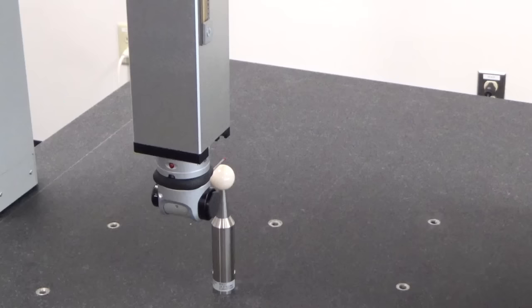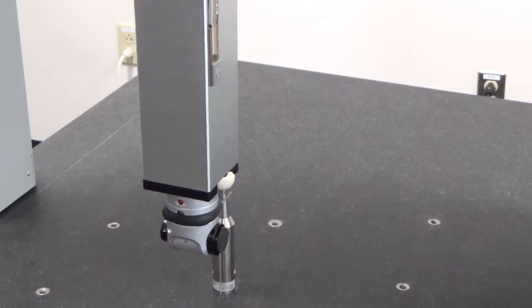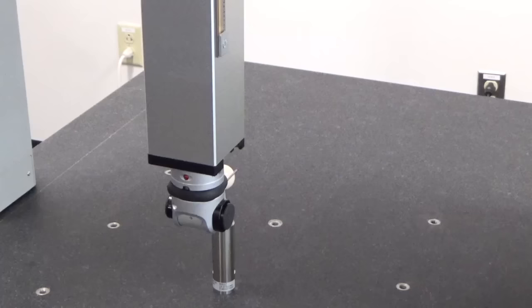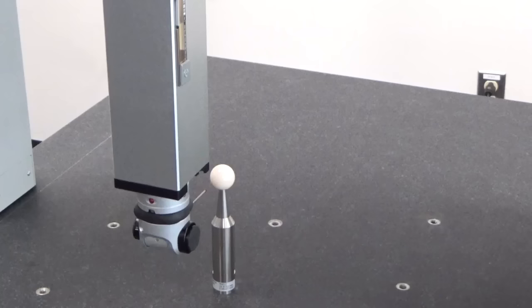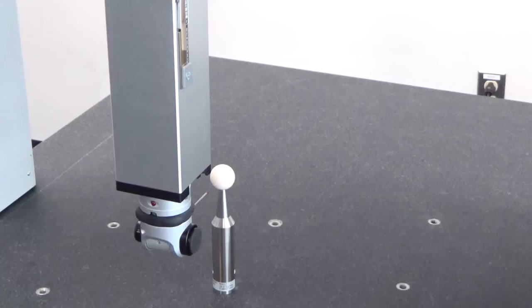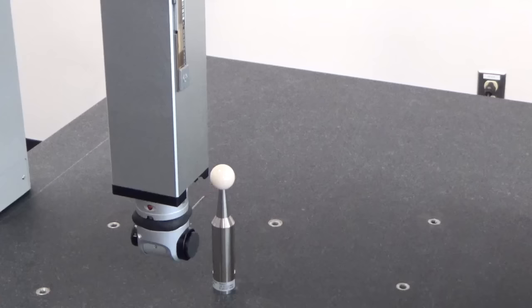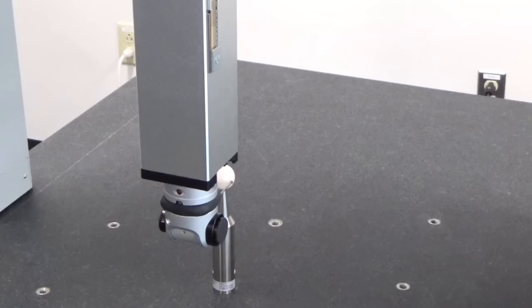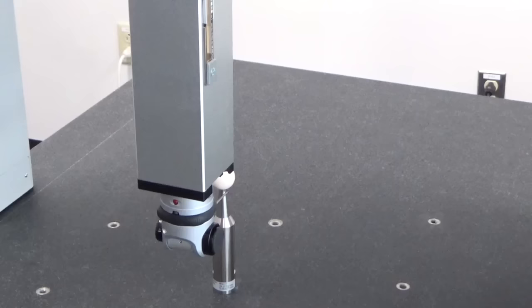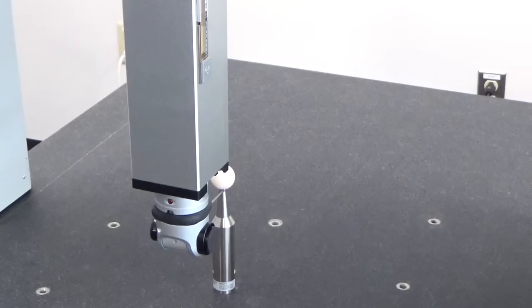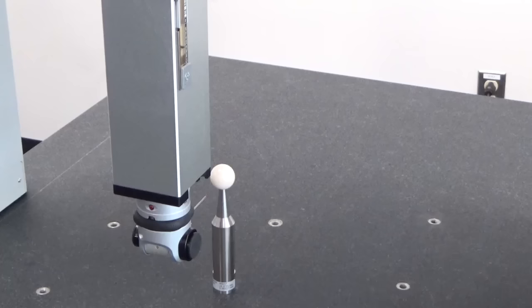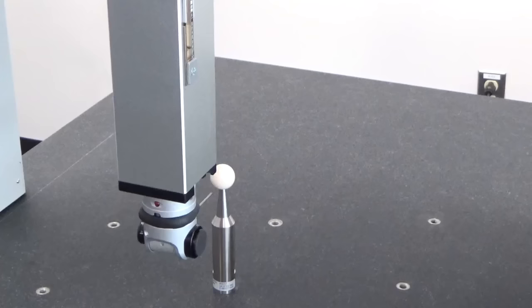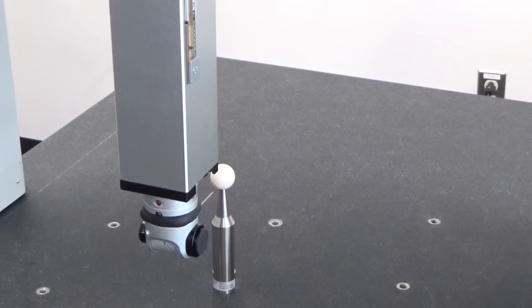So back to the discussion on touch probes. Touch probes can be hit straight on, they can be hit on the side, and they will create the necessary response back to the machine. The only thing that you have to really keep strongly in mind is that when you come in on a part, if the part is at an angle and you touch it, it's only going to sense the direction of the ball in the direction that you approach the part. And as such you may actually be not probing the surface you thought you were. Okay, so we have completed the initial calibration here.